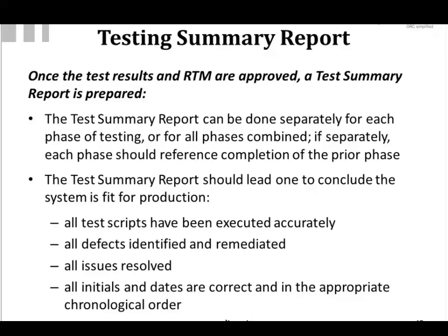You also want to make sure that if some change to your system, your software, is such that it's going to require you to add requirements, delete requirements because you're not going to use those or those don't work, you want to make sure that you treat every one of these documents as a living document, and you go back and actually update your requirement specification to be current, and then complete your set of testing beyond that.